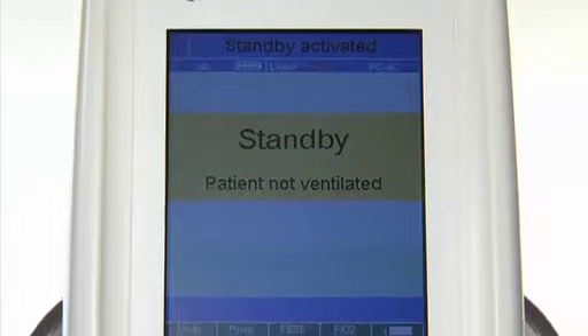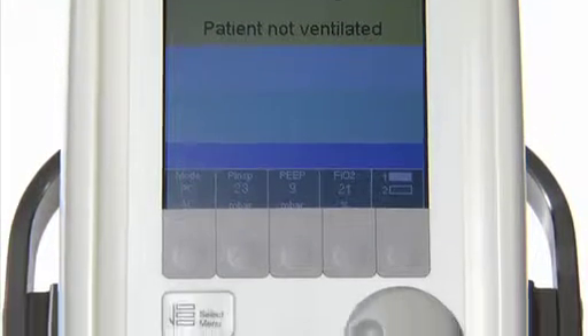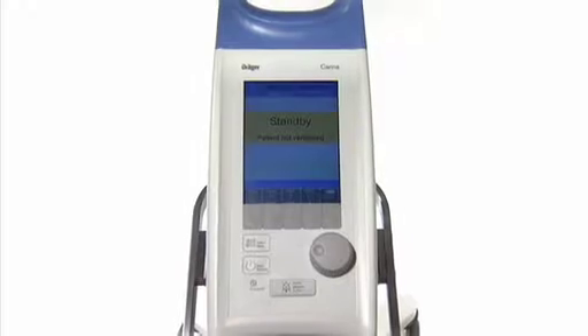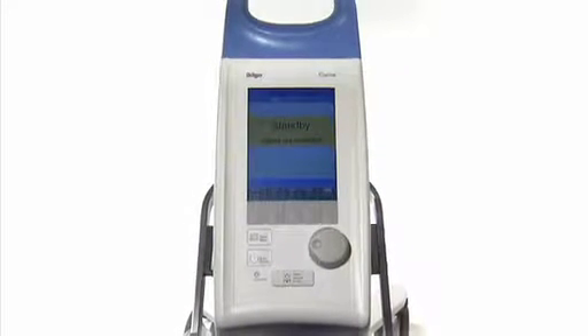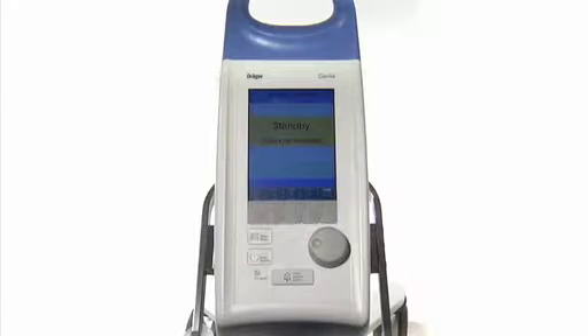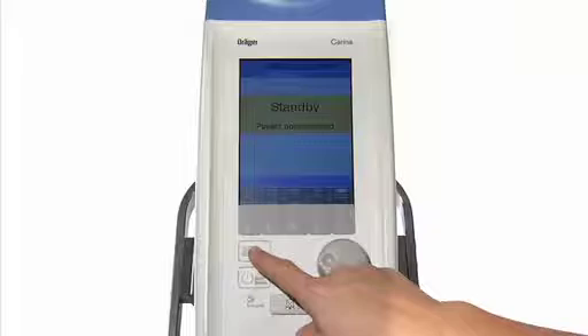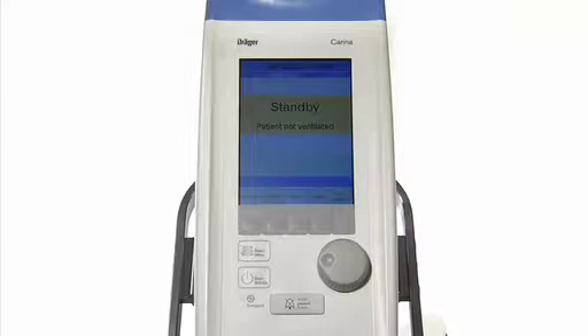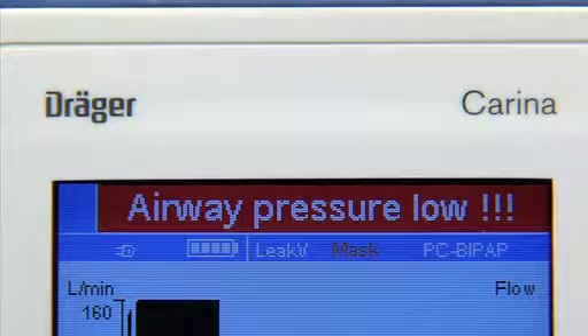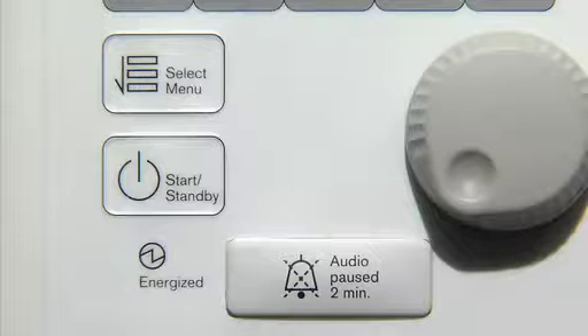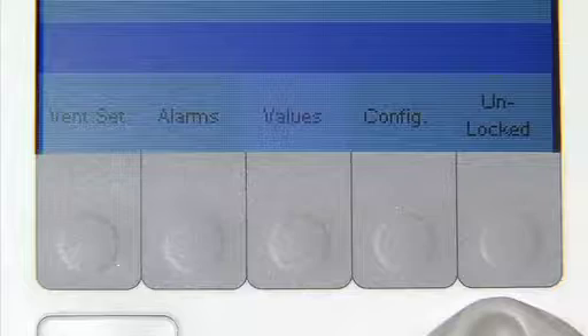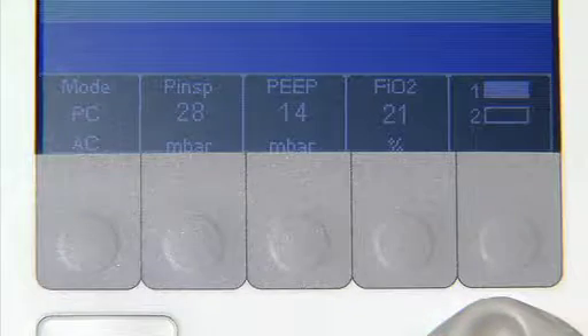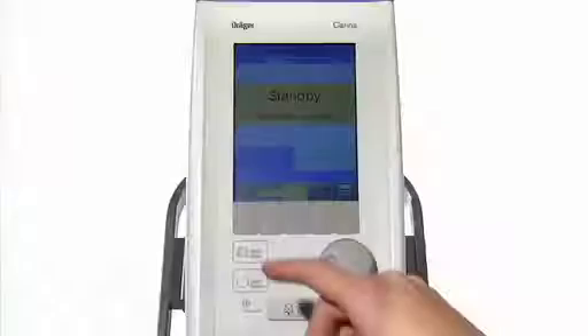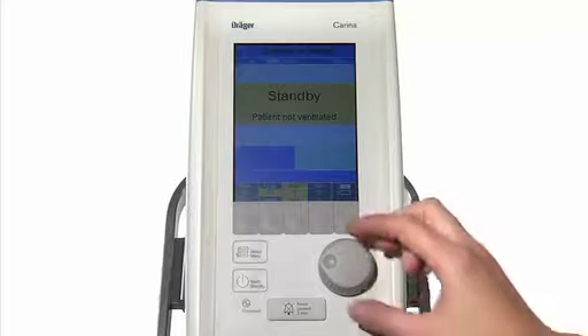The high visibility TFT color screen displays value or curve information which can be easily customized to provide exactly the information you need. Several buttons and one rotary knob ensure intuitive operation. Pressing the Select Menu button lets you switch easily from one menu to the next. The Audio Paused button silences an active alarm. Silencing an active alarm will not prevent a new alarm from sounding. Use the 5 buttons below the display to choose the displayed setting options. A selected setting can then be adjusted by simply turning the rotary knob.